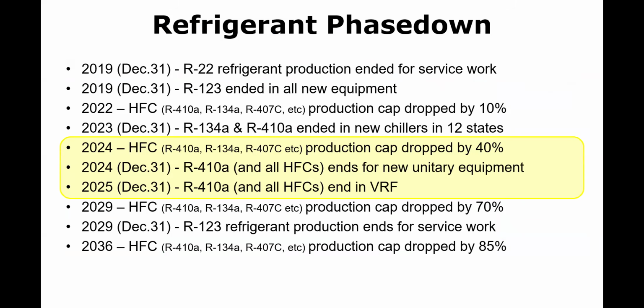In terms of the timeline, this change is significantly faster than the R22 to 410A transition. We started that in 1996 with 410A coming out, and we didn't get rid of R22 until 5 or 6 years ago. So it was a pretty long transition, 20 plus years. This is not that. This is basically a 1 year transition. New refrigerants just started coming out last year, as far as most manufacturers are concerned, and by the end of this year, we're not going to have 410A. So maybe a 2 year transition if you count from the beginning to the end.